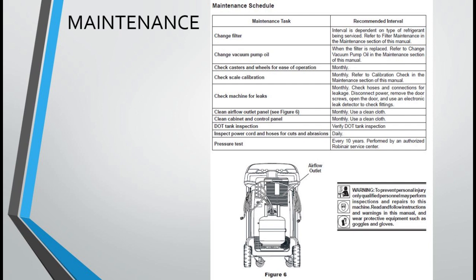Change vacuum pump oil, along with the filter change. Check casters and wheels monthly. Check scale calibration. Monthly check machine for leaks. Clean airflow outlet panel. Clean cabinet and control panel. Monthly DOT tank inspection. Verify DOT tank inspection. Daily, inspect power cord and hoses for defects. Pressure test every 10 years by an authorized service center.